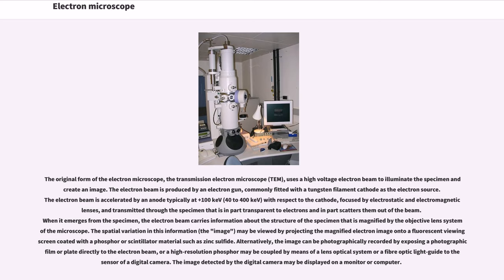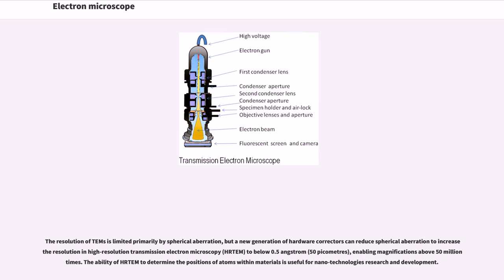The image detected by the digital camera may be displayed on a monitor or computer. The resolution of TEMs is limited primarily by spherical aberration, but a new generation of hardware correctors can reduce spherical aberration to increase the resolution in high-resolution transmission electron microscopy HRTEM to below 0.5 angstrom, 50 picometers, enabling magnifications above 50 million times.